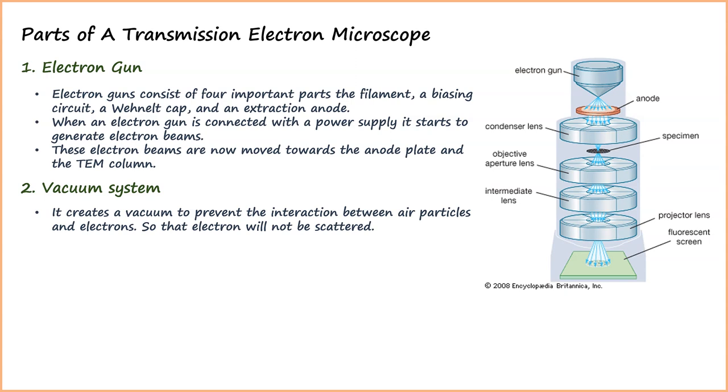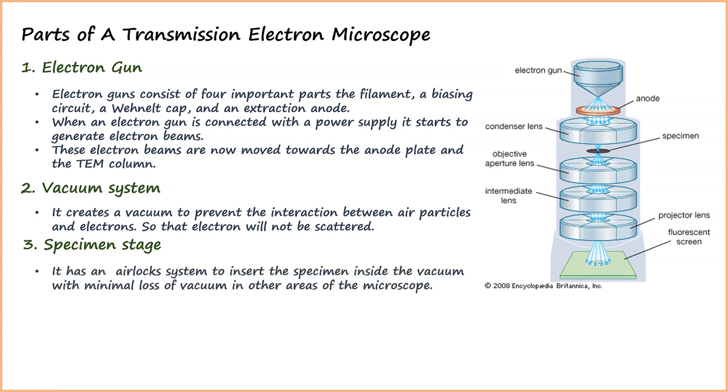The third part is the specimen stage. It has an airlock system to insert the specimen inside the vacuum with minimal loss of vacuum in other areas of the microscope.